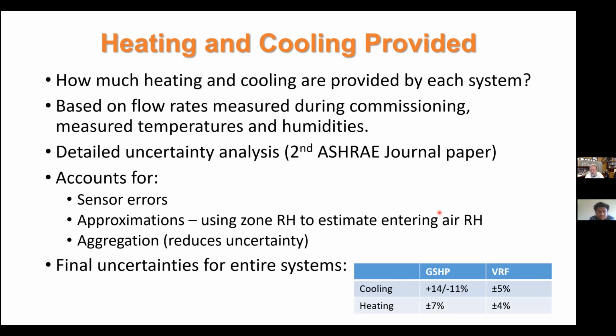I cut this down to try to get my talk into 45 minutes, but it's based on flow rates measured during commissioning, measured temperatures and humidities. And the flow rates were measured at different thermostat stages so that later, when the system was operating, we knew what stage it was at, so we could determine the flow rate. And that was true for the VRF system up until April 2012.